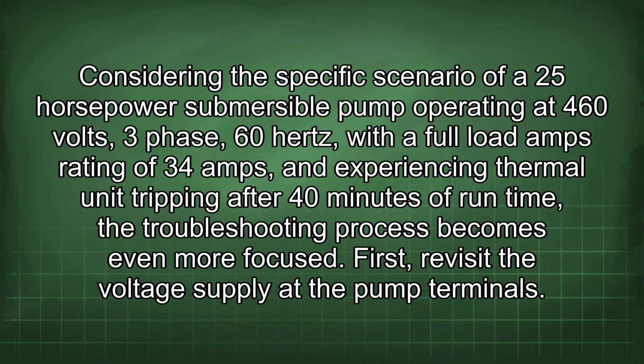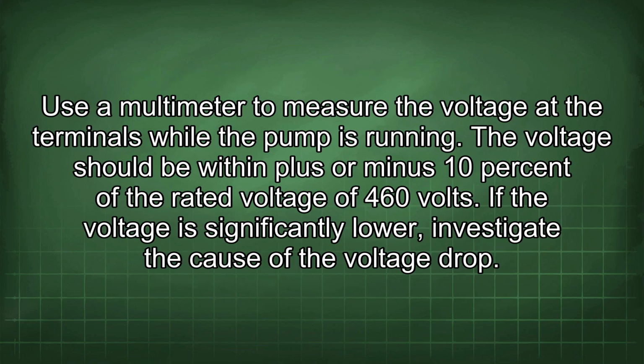Considering the specific scenario of a 25 horsepower submersible pump operating at 460 volts, 3-phase, 60 Hz, with a full load amps rating of 34 amps, and experiencing thermal unit tripping after 40 minutes of runtime, the troubleshooting process becomes even more focused. First, revisit the voltage supply at the pump terminals. Use a multimeter to measure the voltage at the terminals while the pump is running. The voltage should be within plus or minus 10% of the rated voltage of 460 volts.